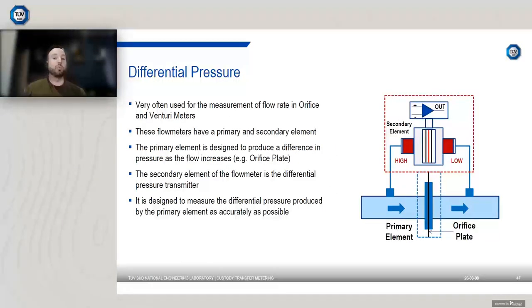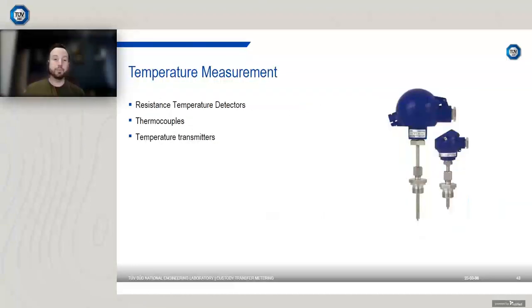Now, why is differential pressure important? It's often used for the measurement of flow rate in orifice and venturi meters. These flow meters have the primary element in the orifice plate, the plate that's causing the restriction. The secondary element is the differential pressure transmitter. The performance of an orifice plate is highly dependent on the measurement of differential pressure. So it's important that whatever method you use to measure differential pressure, you're measuring it to a low uncertainty.